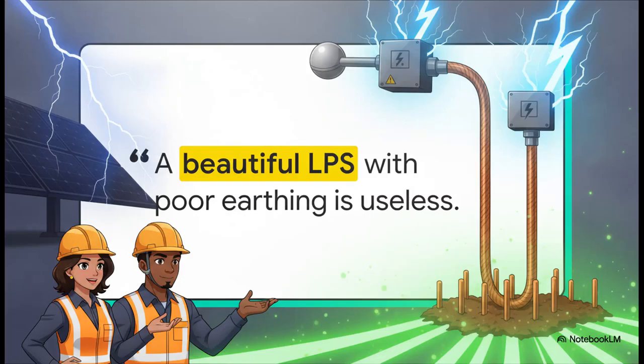Which leads me to leave you with this exact quote from our training guide: "A beautiful LPS with poor earthing is useless. Your mathematically perfect rolling spheres, your top-tier Type 1 SPDs, your shiny copper down conductors, they're only as strong as the earth connection beneath them. All that lightning energy has to go somewhere, right? And if that path isn't a measured, low-resistance connection directly to the ground, it's going to find its way through your million-dollar equipment, or much worse, your personnel." So, knowing all this, are you ready to design with absolute confidence on your next utility-scale site? Keep these steps close, trust your calculations, and I'll catch you in the next explainer.